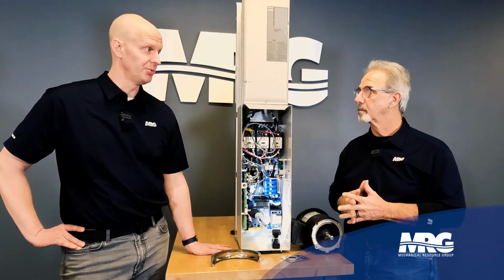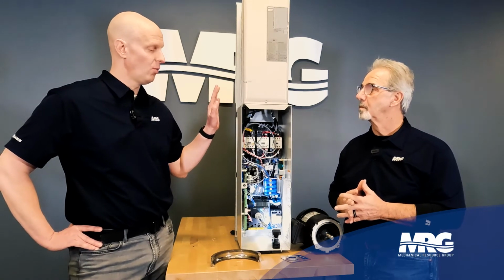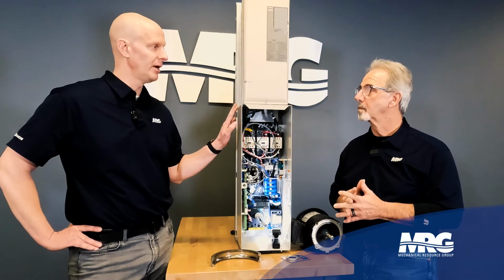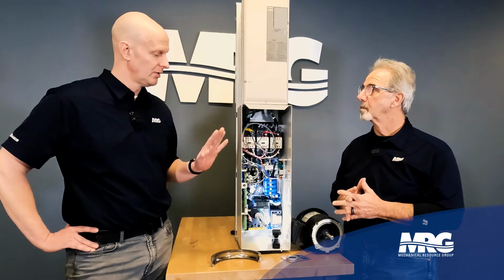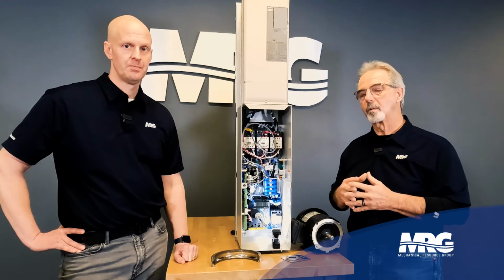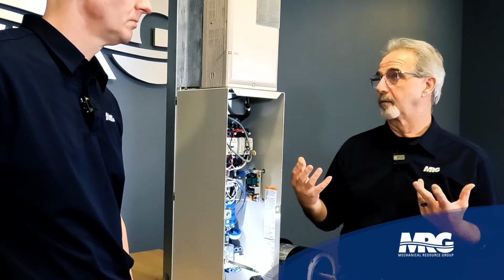Absolutely. When you're running motors with a VFD. So tell me, one last question. So at what size drive, what size motor, when would I apply a CoolBLUE solution to protect my motor bearings? Well, they're rated by horsepower and they're rated by length of lead. And there's a point of diminishing return at some point in time. When you start talking in the fractional horsepower, all the way up to 5 horsepower, we can replace those motors for about $300 to $500.